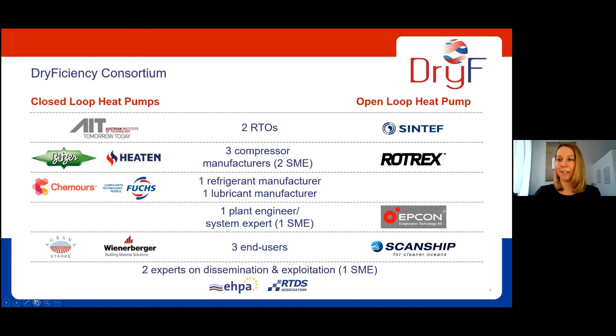So let's have a closer look at the technology. Here you see a sketch of the closed loop heat pump. I want to start with the evaporator, because this is where the waste heat comes in. We use waste heat with temperatures around 80 degrees C to evaporate the refrigerant. Our refrigerant is Opteon MZ, the trade name for R1336mzz(Z), a low GWP refrigerant developed for high temperature applications.